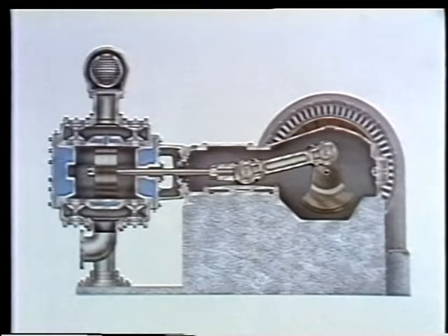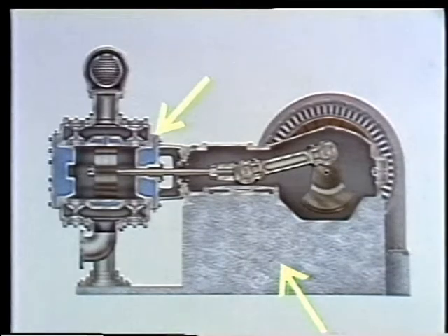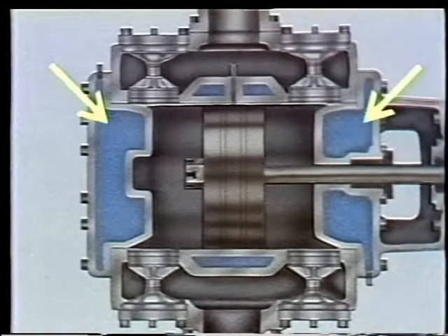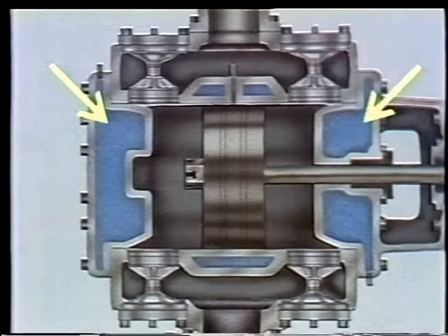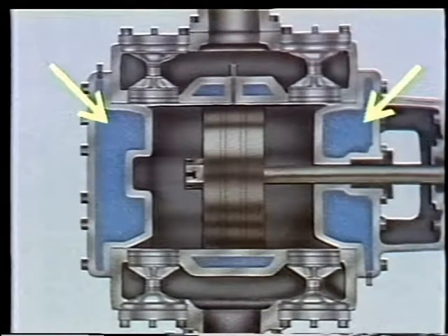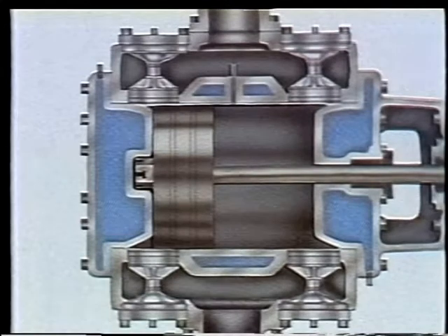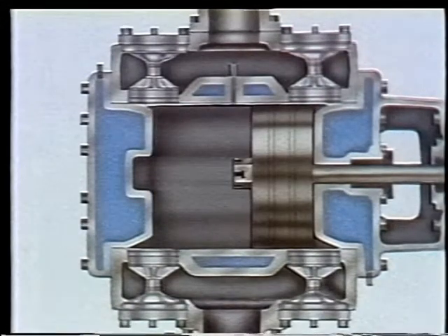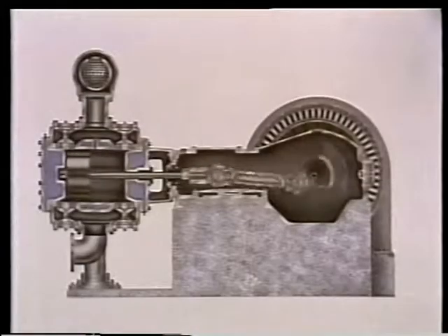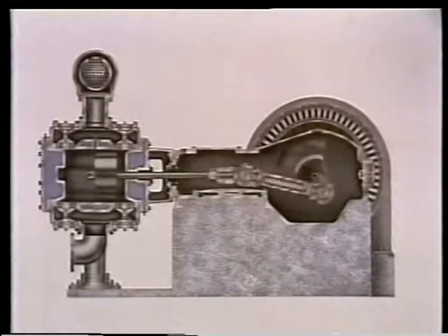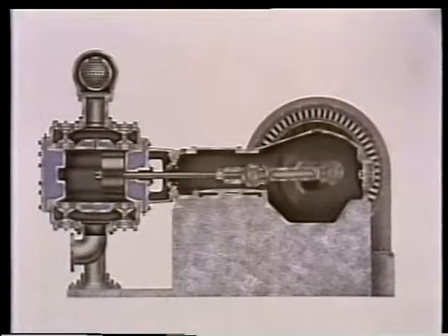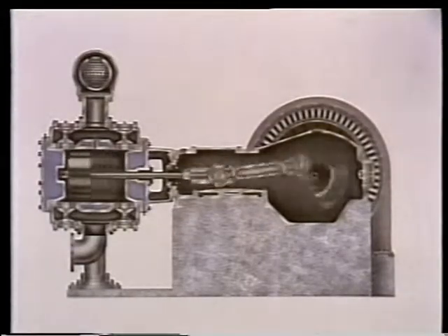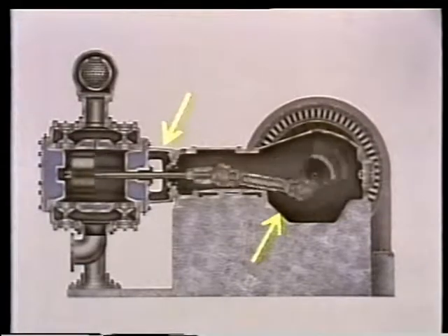We can also see the compressor's foundation, its casing, and the cylinder. Attached to each end of the cylinder are the heads, and they are commonly referred to as the top head and bottom head. The top head is where the piston stops when it's on an upstroke. The bottom head is where it stops on a downstroke. The foundation is a reinforced concrete pad which minimizes vibration by providing a firm base to counteract the movement of the parts inside. The casing is mounted on the foundation.